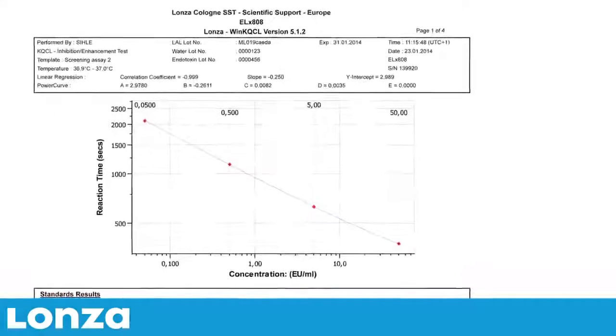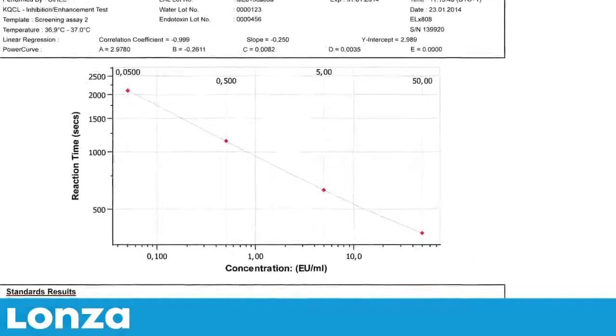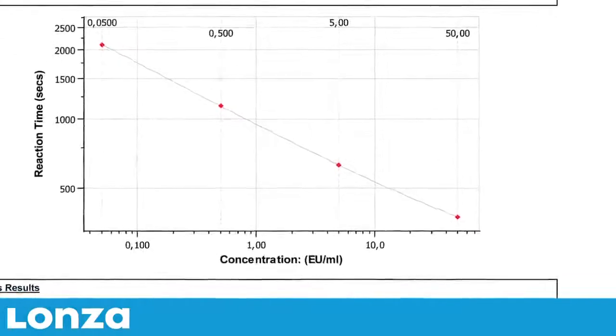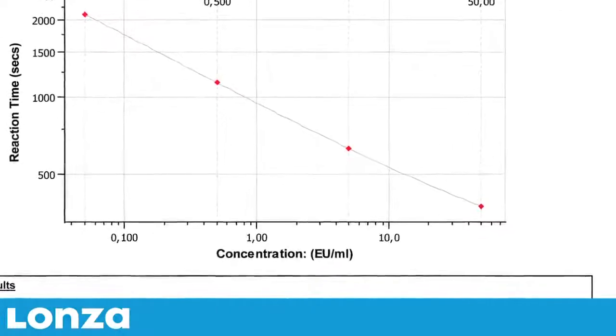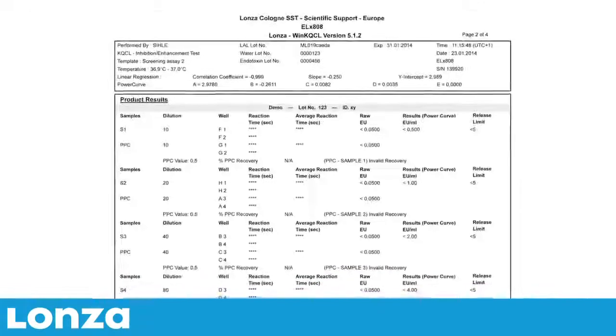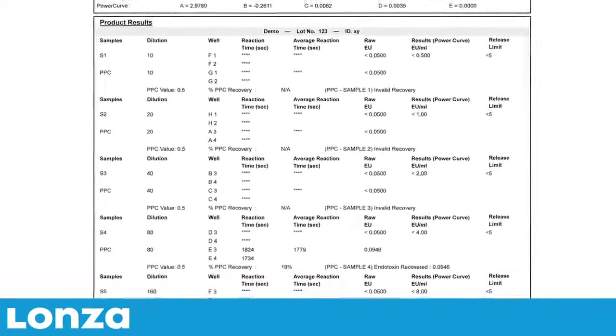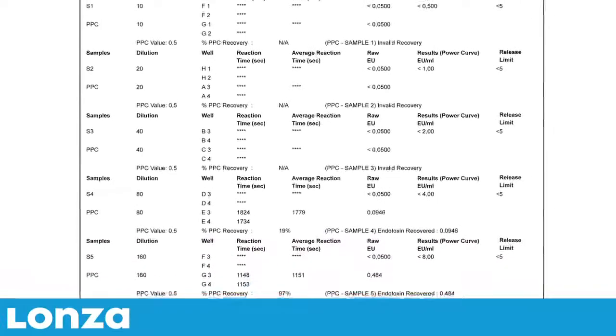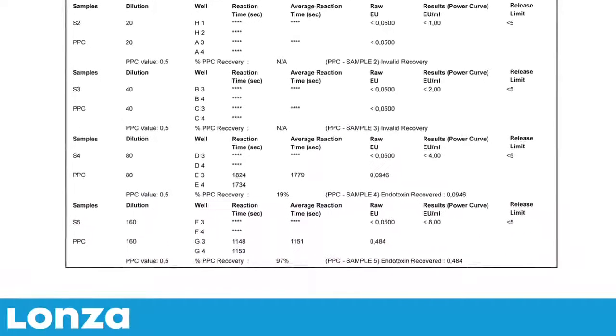The WinKQCL software automatically creates a standard curve via a log-log linear correlation of the reaction time of each standard with its corresponding endotoxin concentration. The endotoxin concentrations for the unknown samples are then read from the standard curve.